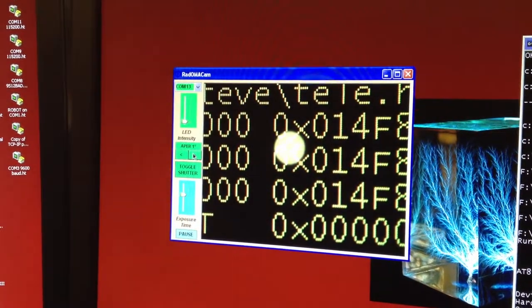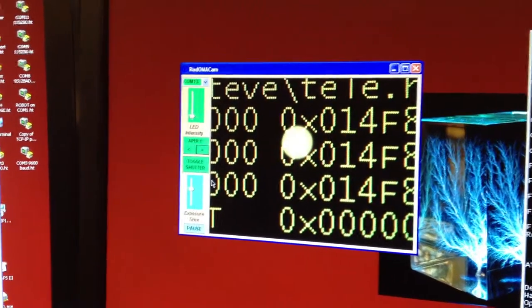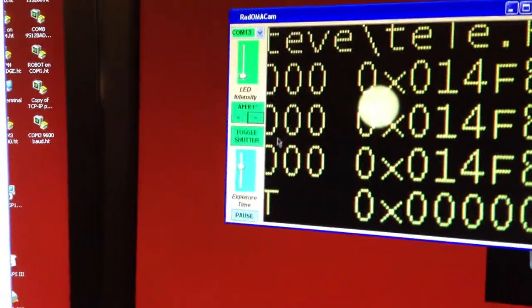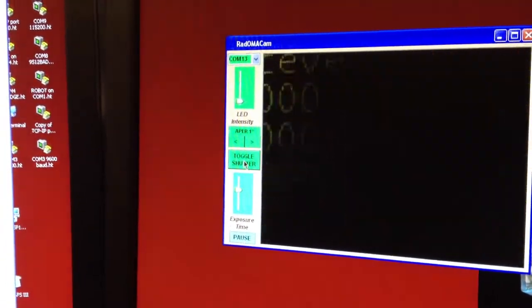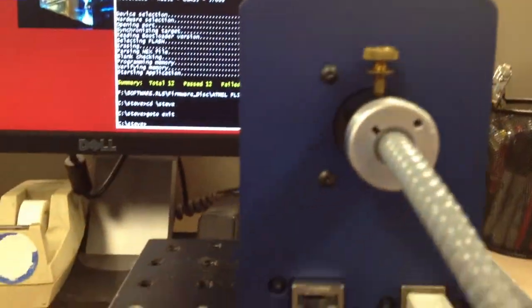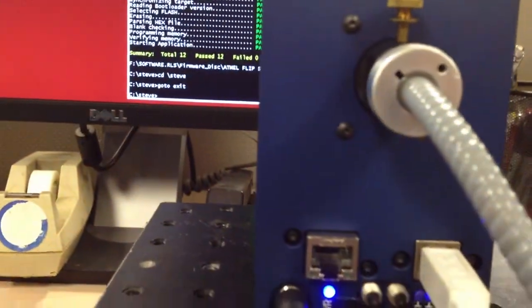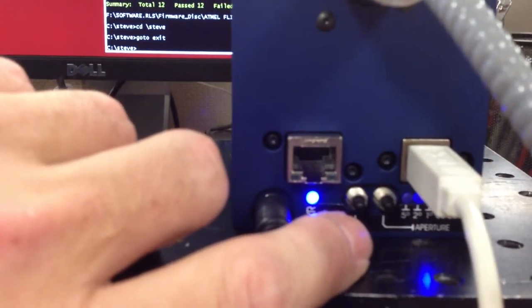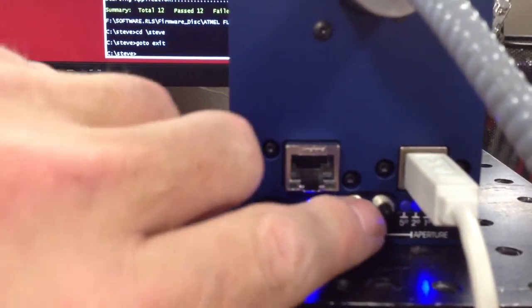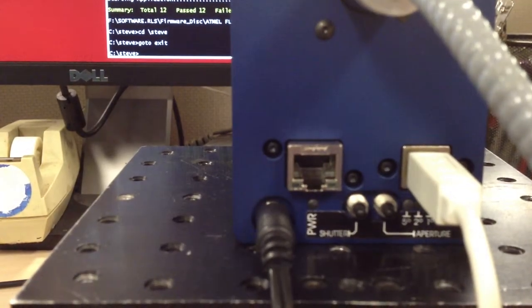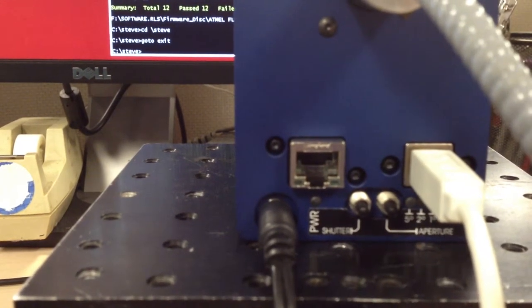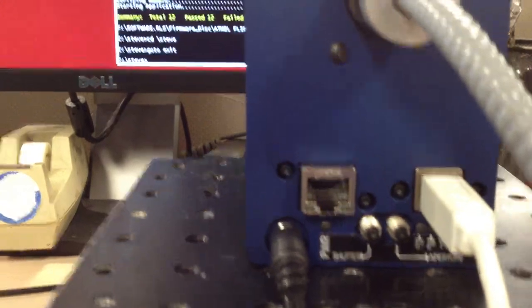When you're ready to take a scan with the Radoma you have to put it in measure mode instead of view mode like it's in now, so you say toggle shutter. At this point the fiber is looking at what we were just looking at a moment ago. And this button on the left is the same thing. It toggles between view and measure mode, just push it. All the lights go out so that when you're actually making the measurement there's no light contaminating your setup.